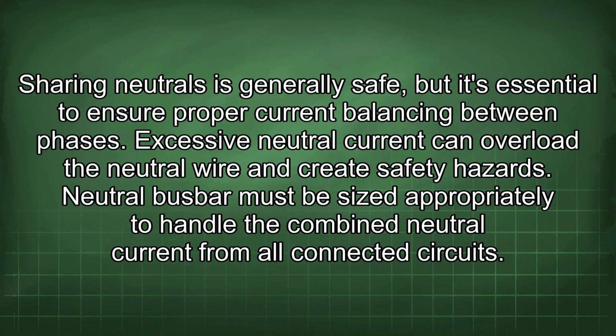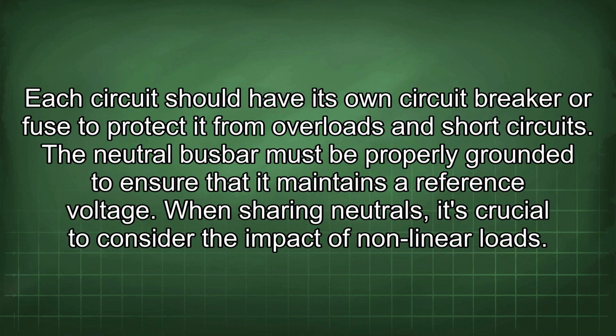The neutral busbar must be sized appropriately to handle the combined neutral current from all connected circuits. Each circuit should have its own circuit breaker or fuse to protect it from overloads and short circuits. The neutral busbar must be properly grounded to ensure that it maintains a reference voltage.